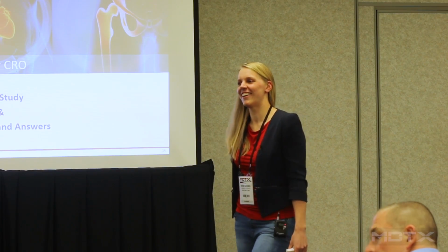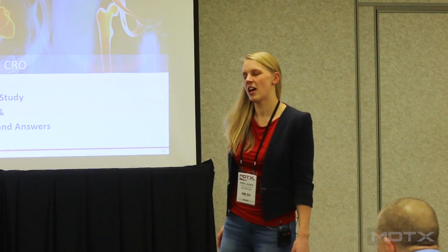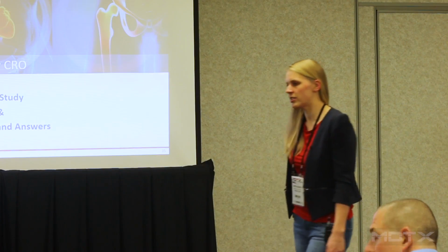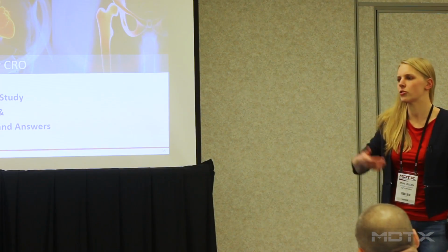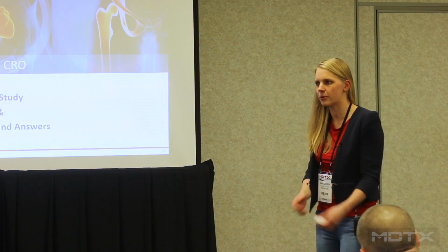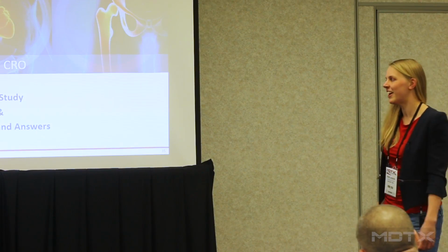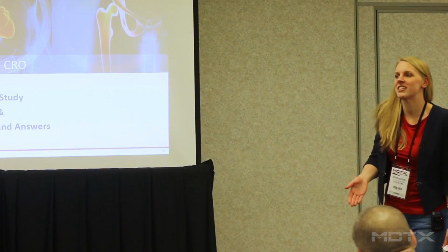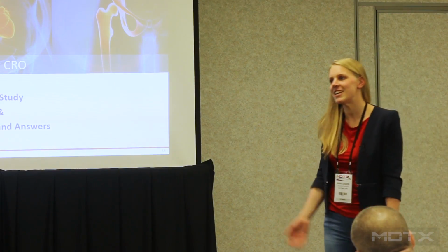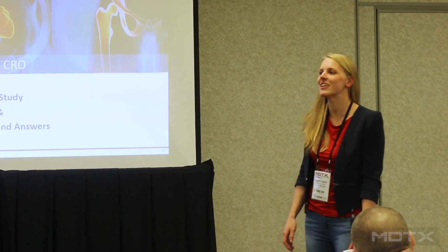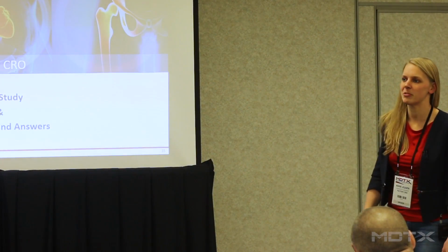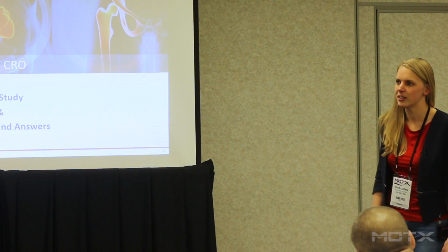Does the MDR require a CER for class 1, self-declared types of products? Yes, the MDR requires CERs for every device you have on the market. And we often have questioned whether it's a different kind of structure, or whether you have a different process, or whether it takes us fewer hours. You have to go through the same process. You just won't have much data, so it's very difficult to make a story of it. That's easier for your class 3 devices where you did perform studies.